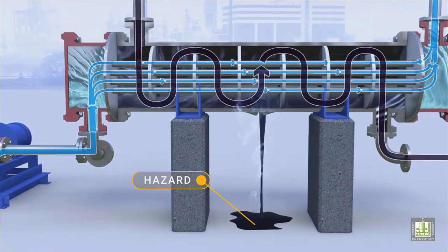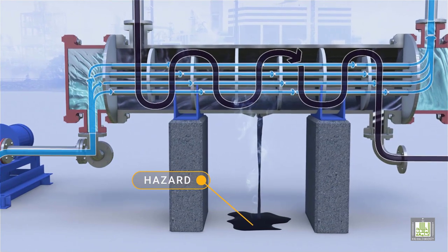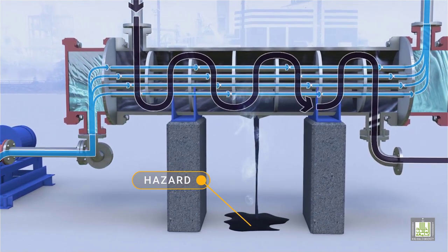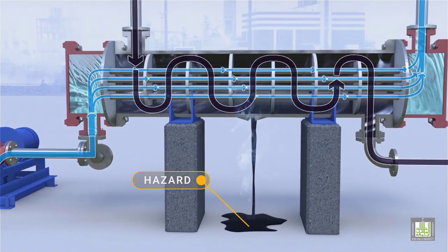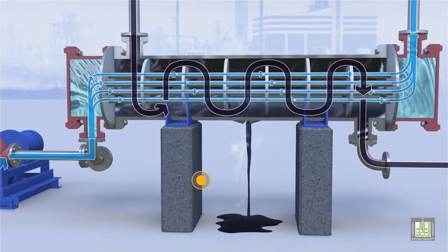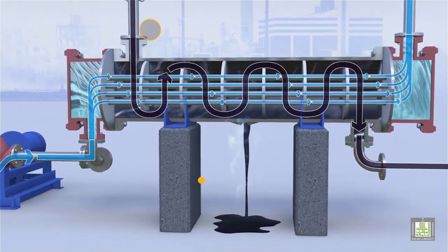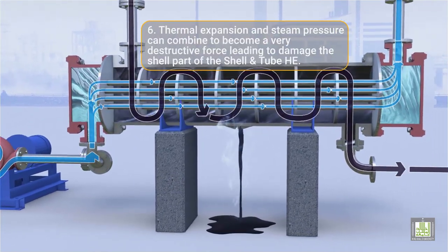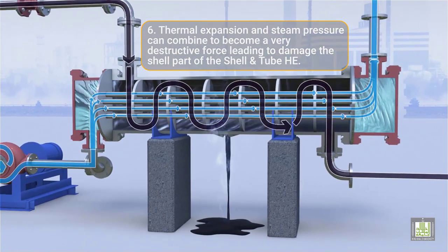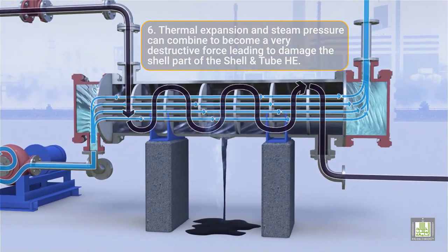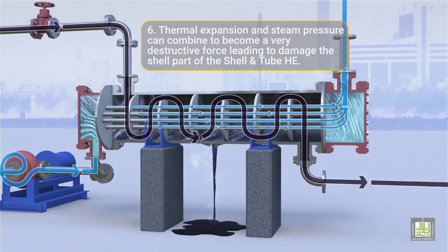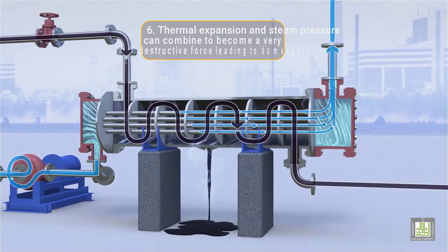Uncontrolled mixing of water with hydrocarbons can generate high-pressure conditions and can damage systems that are not equipped with pressure-relief devices. Thermal expansion and steam pressure can combine to become a very destructive force, leading to damage of the shell part of the shell and tube heat exchanger.